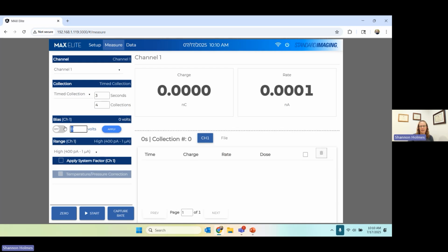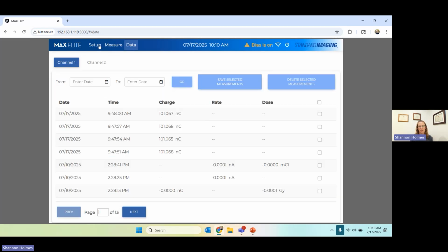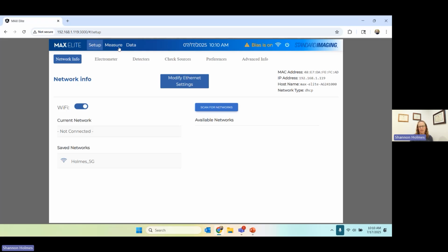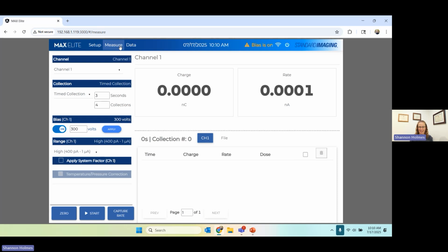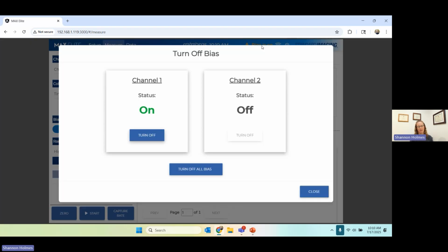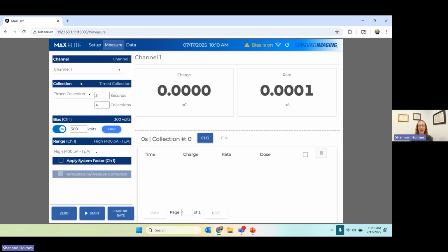When I apply bias here, I can choose the voltage and turn it on. It'll show you the actual voltage on that channel up here, as well as an indicator at the top of the screen that you have bias turned on. This is one of the little features that I really like about the electrometer, that this bias indicator is visible from any of the pages of the electrometer. So if I happen to be checking my data or doing something else and then realize that I need to get out of the way because there's a patient coming in or somebody else needs the machine, or I just need to move on to something else, I can turn off bias from wherever I am on the device. I also have that indicator that bias is on so that I don't try and disconnect a chamber or connect a new chamber if I've got the bias turned on.